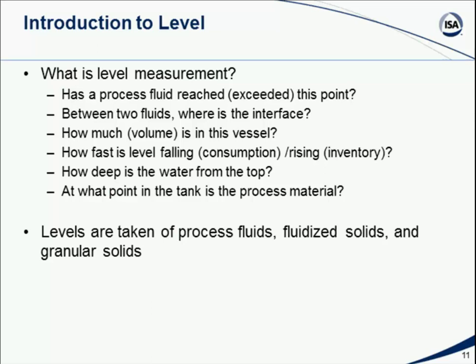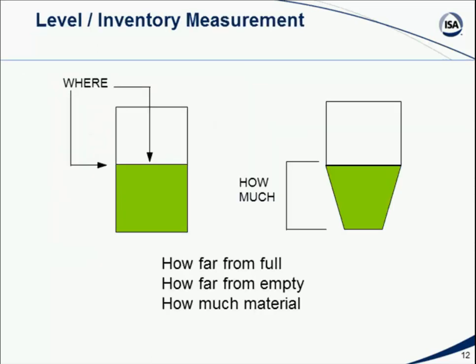because maybe our primary concern is not to overflow a tank. And of course, for a lot of people, when they say level, what they really mean is, where exactly in the tank, vertically from the bottom, is the edge of the processed material. Now, with a liquid, that's easy to identify. With things like solids, dried materials, sands, things like this, that's a little bit more difficult to identify. But we have technologies for all of this, and we do make level measurements on processed fluids, fluidized solids, and even granular solids.